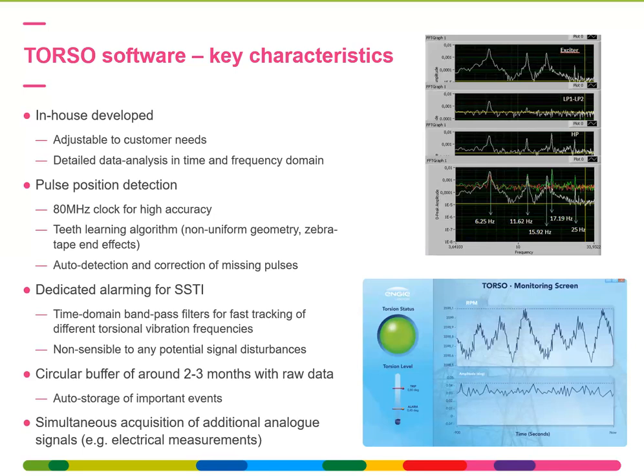You have dedicated alarming for any subsynchronous torsional interaction. This means that you have bandpass filters which are tracking the different torsional vibration natural frequencies. So any resonance phenomenon that you might have will be identified by these bandpass filters. The advantage as well is that you're not sensitive to any potential signal disturbances because you are checking in a narrow frequency band. Circular buffer, as explained, a couple of weeks to months, depending on the amount of sensors, and auto storage of important events.